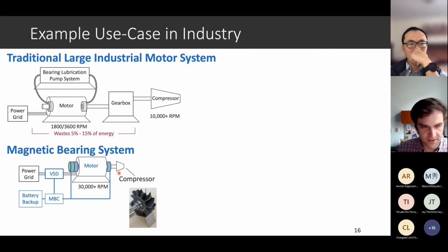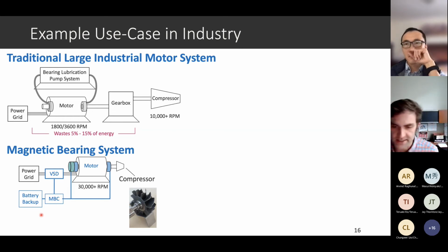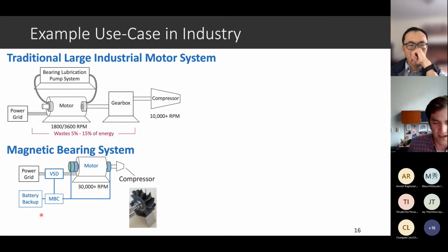When the motor is high-speed, it becomes smaller. When the compressor is higher speed than it used to be, it becomes smaller. Your shaft is levitated by these magnetic bearings we talked about, so you add electronics for the variable speed motor drive, and electronics for the magnetic bearing controller. Now and then you better throw in a battery backup system, because you wouldn't want your shaft to crash down at 30,000 RPM if the power grid glitches.